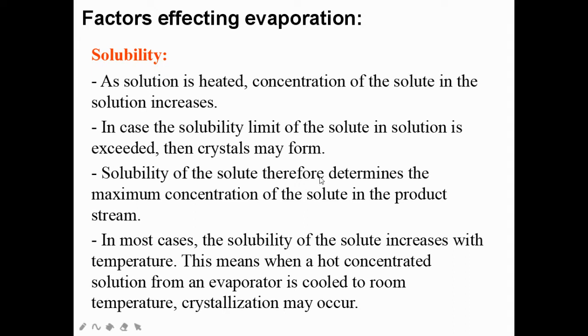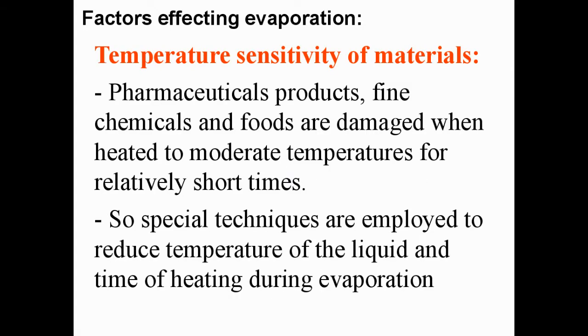Another factor is solubility. As a solution is heated and concentration of the solute increases, if the solubility limit of the solute in solution is exceeded, crystals may form — this is essentially how sugar is made. Solubility of the solute determines the maximum concentration of the solute in the product. In most cases, solubility of the solute increases with temperature, meaning when a hot concentrated solution from an evaporator is cooled to room temperature, crystallization may occur.